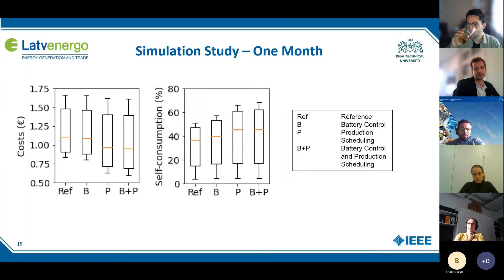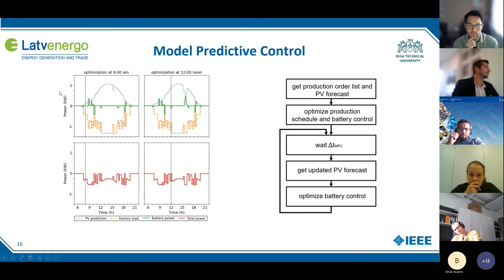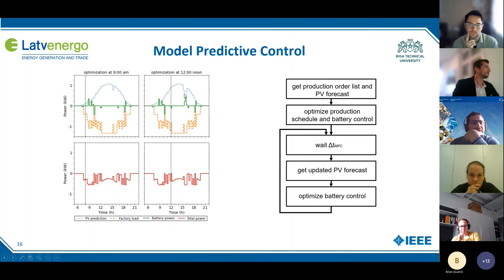We can see this in the model predictive control concept. Here we are using model predictive control to react to weather changes. In the morning, we optimize both the battery control and the production schedule, then we continuously optimize the battery control to react to uncertainties. If we get a new PV forecast with a big drop, we optimize again, resulting in a different battery control. The battery compensates the drop so that the load profile doesn't get a big peak, which would increase the costs a lot.